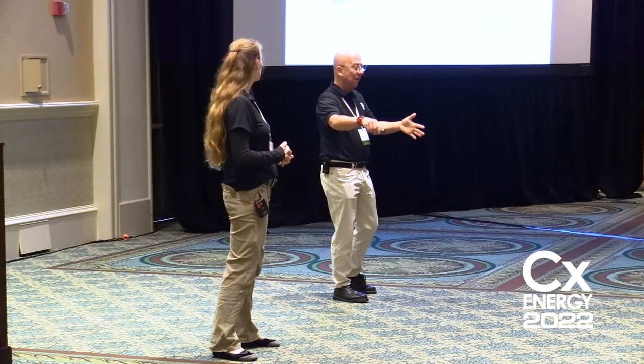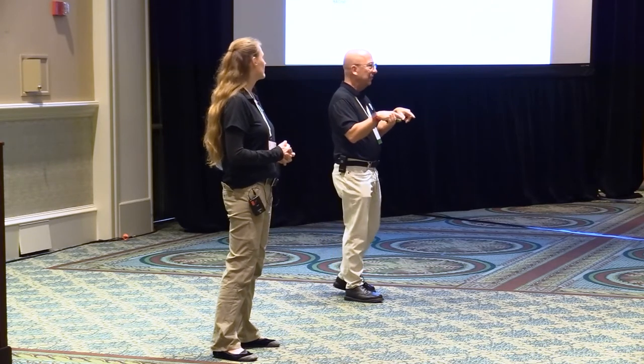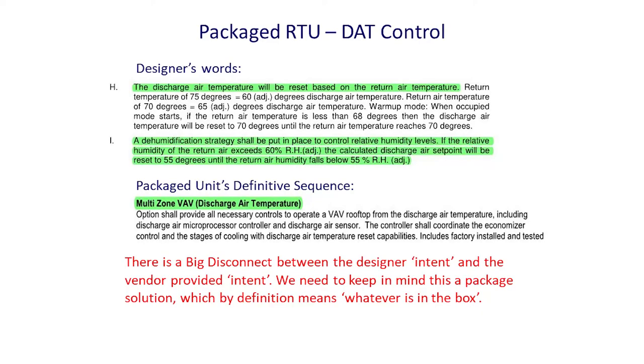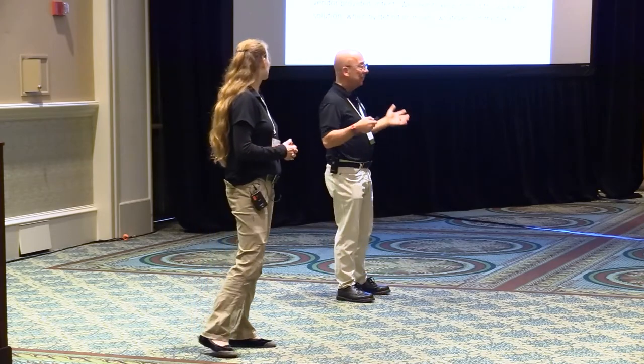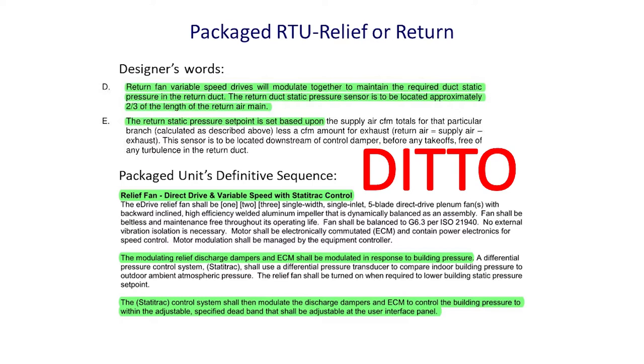Now, I know a lot of controls people say, my drawing shouldn't be used for that, and I completely agree, but it's unbelievable how many people do look at that control drawing schematic, because sometimes that's the best one. Sometimes even the designers don't put a good enough schematic, and it's just a really good picture of how something should operate. And here is an example where the designer's words do not match the words from the packaged unit's manual. So there's a big disconnect. The designer is saying, I want this discharge air reset, and the package is saying, this is how I do it. And this is an example, also on the next slide, I'm using the word ditto there, where the mechanical engineer created this situation and had the control contractor go down a bad rabbit hole, right?